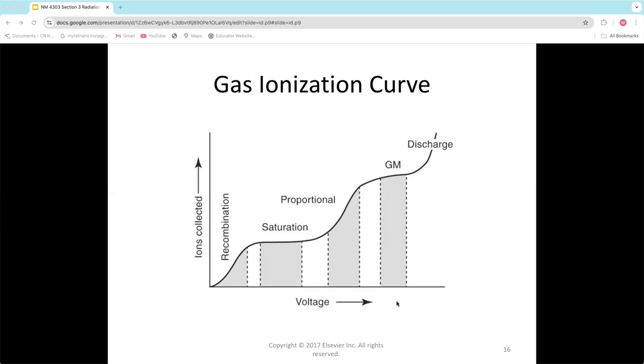Well, as you increase the voltage, that's how we begin to get reactions that we can measure. The next range you'll need to look at is the saturation range. Some books also refer to this saturation range as the ionization range, but it's called the saturation range as well. So you have this middle range. What's happening in this range is that you get separation, and there's enough voltage that it attracts the ion pairs and the electron to the cathode and the anode. So you get this separation, and when that happens, you get a current in the system. And when that current happens, that's what gives you a reading.